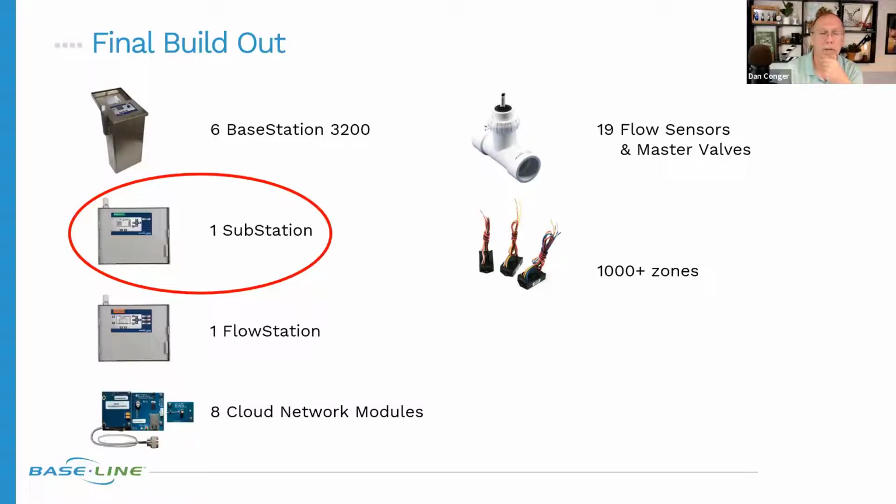And what I thought was really interesting and cool was the ability to adapt on the fly, relatively easy. Now Andy, do you see more substations on new installations or retrofits? Typically retrofit, yeah. Because the retrofit was pieced together over time, where there was a controller and it was 24 zones, and that's all it had. They expanded, then they dropped another controller and another controller and another controller. And oftentimes all of those multiple controllers have one water source, and that becomes a programming and scheduling nightmare.